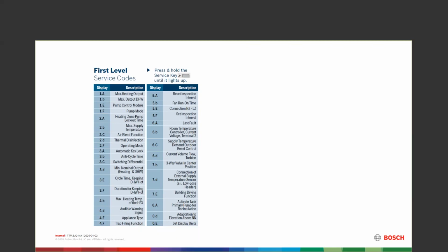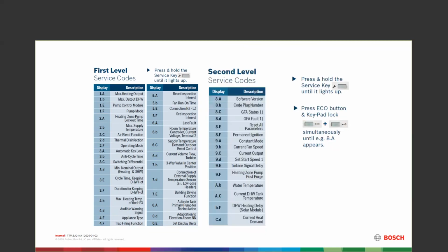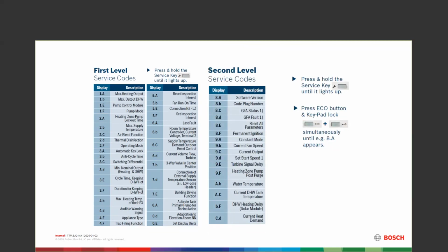At higher elevations, above 2,000 feet, you're going to go in and reset that, and that gives you your elevation. So once you've done your first service level, you're going to go to the key lock button and the eco button at the same time and press and hold those. It's going to come up with this whole next thing. So you're going to see 8A. That's what software version is. 8B is what code plug is in it. 8C and D don't do much of anything. They're just there. 8E, as in Edward, is a reset of the control back to factory settings.